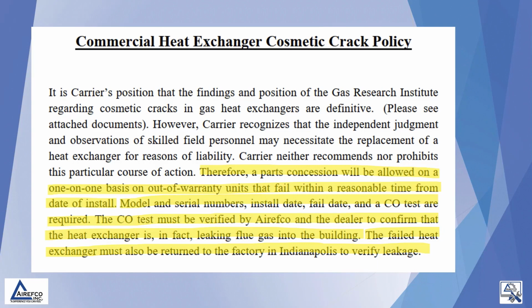This is a statement from Carrier after the Gas Research Institute did extensive testing on the cosmetic cracks. They found no leakage of carbon monoxide through the cracks. However, Carrier, recognizing the liability a tech may feel in the field, has put in place a procedure to replace heat exchangers with cosmetic cracks. If within a reasonable time out-of-warranty units fail, they will allow a replacement of the heat exchanger under warranty.